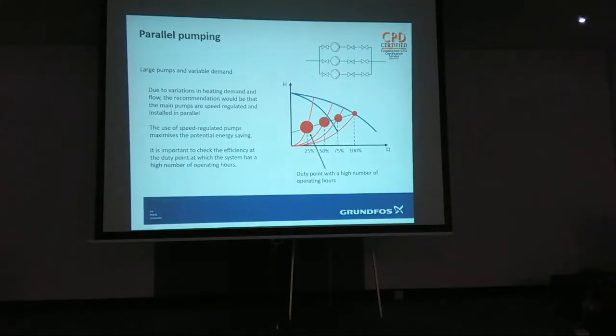Because the maximum duty and the minimum duty are so far apart, you end up with about 10 pumps all the same to do it, so you've got to put a jockey pump in that instance. When you're down here, a lot of pumps can work in this area, but in the middle of the night, middle of June, with no demand, water's going out at 82 degrees C and it's come back at 81.5. It's so well insulated, nobody's using anything, you've still got to have the water going out. And you don't put a bypass around the pump. Please don't put bypasses around the pumps.